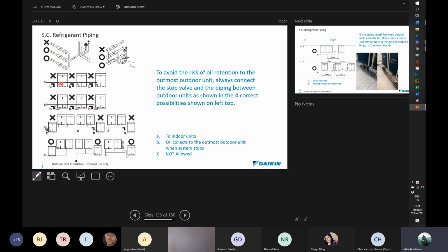Right. On this topic, again, do not come in above. It's the same type of thing. Even if you come in above and then go in and under and below, you haven't solved the problem of the oil wanting to go to the first unit. You've still got the same issue there. When units are placed at different heights, which can happen especially when installing on the side of mountains, you need to take particular note of the correct way of installing. You cannot come in at a height where the first piping is above these service valves and then go underneath. The piping must be below the lowest unit service valve and then go up. And in the instance over here, when you're coming in like that, you can put a gas riser on the unit into the last unit. So take note of these.